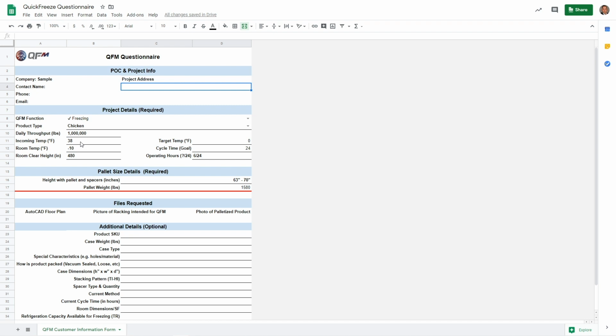Next thing we're going to do is input our expected incoming product temperature. In this example, it's 38 degrees. That's a pretty common inbound fresh product temperature. The next piece of information we're looking for is anticipated room temp. In this example, we're going to run at -10 Fahrenheit. The next thing we look at is the clear height of the room, and that's really for system modeling and projection. Next is our target temp for the product. Most freezing projects require a 0 degree product target temperature, so that's what we're going to run with in this example. And then we look at the intended cycle time. In this example, we're running with 24 hours.